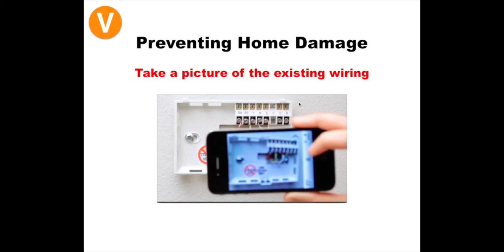And if that isn't caught and runs for a long period of time, that's never good for the customer's system, and it doesn't help when it's summertime and maybe their heat is working instead of their cooling. Customers don't like that. It can cause problems and blow fuses and transformers. So if you take a picture of the customer's wires, it takes all the doubt out of play, and you can refer to your picture to make sure you're getting the correct wire in the correct terminal.